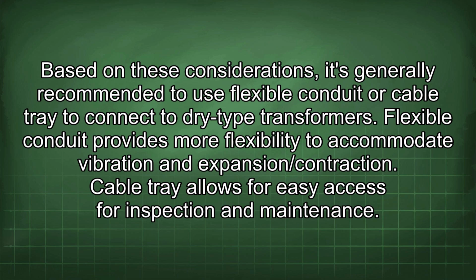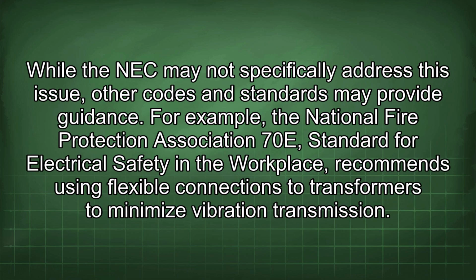Based on these considerations, it's generally recommended to use flexible conduit or cable tray to connect to dry-type transformers. Flexible conduit provides more flexibility to accommodate vibration and expansion/contraction. Cable tray allows for easy access for inspection and maintenance. While the NEC may not specifically address this issue, other codes and standards may provide guidance. For example, the National Fire Protection Association 70E standard for electrical safety in the workplace recommends using flexible connections to transformers to minimize vibration transmission.